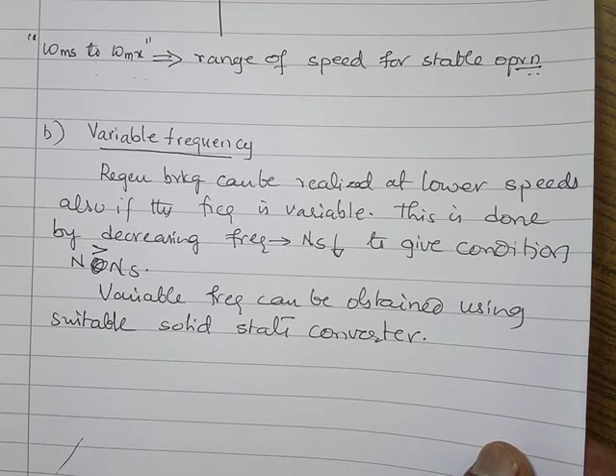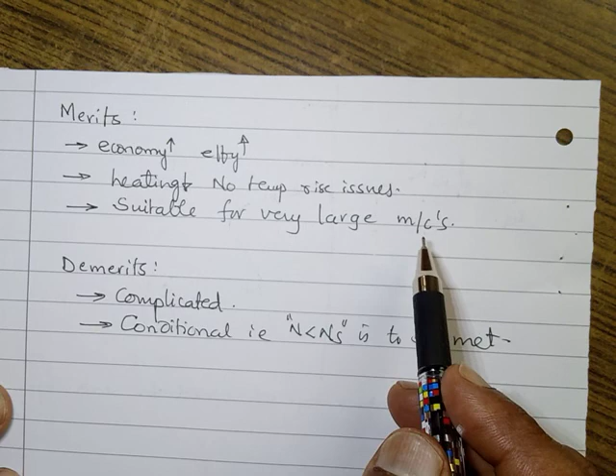Is it okay? Then this method, regenerative braking, has merits: more economy, and efficiency is more because energy is not wasted, and heating is less because energy is not lost in the rotor, it is taken. No temperature rise issues, and it is suitable for large machines because when machines are very large, the regenerative method seems to be the only method, as dissipation of heat poses a very big problem. The disadvantage is that it is complicated, and the condition n less than ns is to be met. That's why it becomes complicated. Otherwise, the regenerative method is a very good method, no doubt about it.